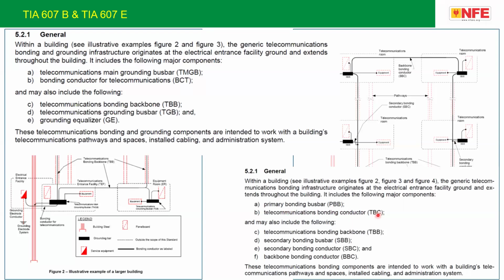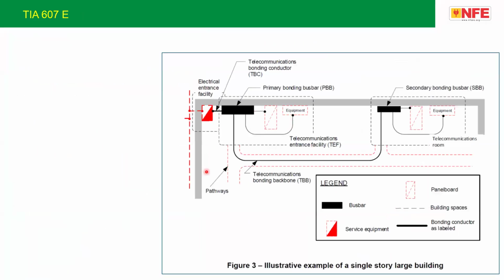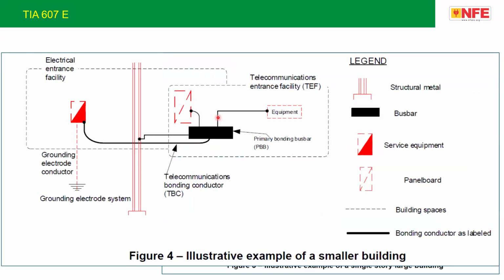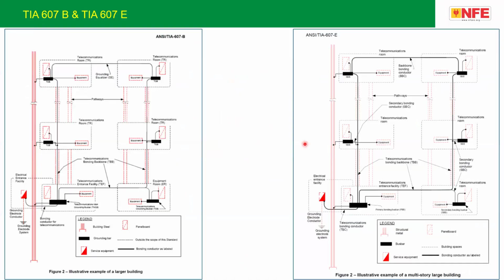Now, if you look at these pictures, for example figure 2, 3, and 4, I am just showing you figure number 3. You can see here different equipment within the building are finally connected to a primary bonding bar. This primary bonding bar goes to the entrance facility. That means whatever the power supply you are taking from there, it goes to the grounding conductor. Basically, the standard TIA 607 says inside these telecommunication rooms, you have to have a bonding, as you can see in the picture.